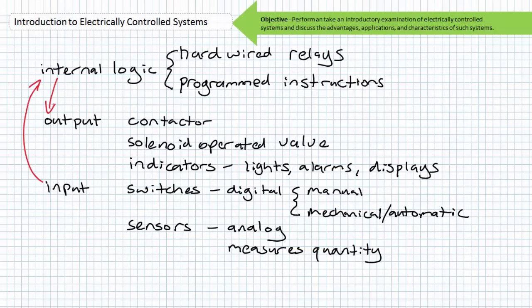Devices or programmed instructions internal to an electrically controlled system are those components that do the actual comparison of inputs and issue outputs. This is where electrically controlled systems employing traditional hardwired relay-based ladder logic and those employing PLCs radically divide. Both types of systems require input in the form of switches or sensors, and both types of systems issue outputs to contactors or solenoid-operated valves or indicators like pilot lamps.